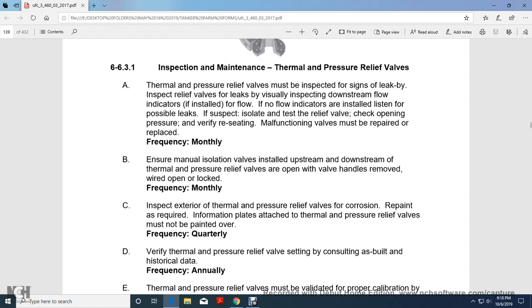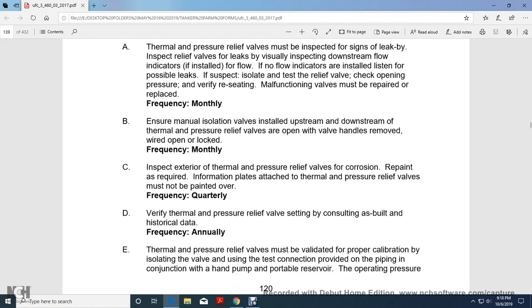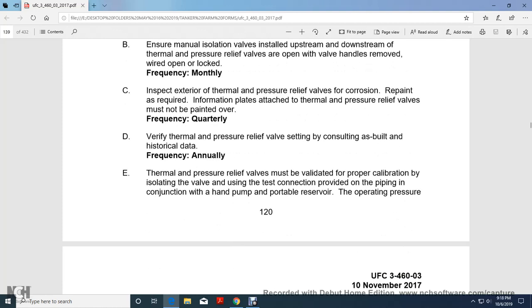Ensure the manual isolation valves installed upstream and downstream of the thermal pressure relief valves are open, with the valve handles removed or wired open and locked, monthly. Inspect the exterior of thermal pressure relief valves for corrosion and repaint. Required information plates must be attached, and thermal pressure relief valves must not be painted over, quarterly. Verify the thermal pressure relief valve setting by consulting as-built and historical data annually.